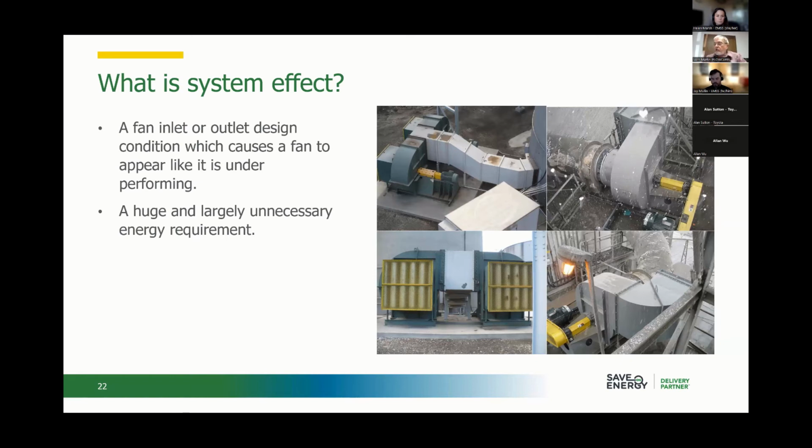So let's take a look at the pictures on the right of your screen. Here we have two fans. I saw this first and was so impressed that I climbed up a ladder and took a picture from above. Essentially, we have two fans blasting air right at each other. Does this seem right to you? You start wondering: if one fan gives a little more flow than the other, could it overcome the other to the point where one fan actually moves no air at all?